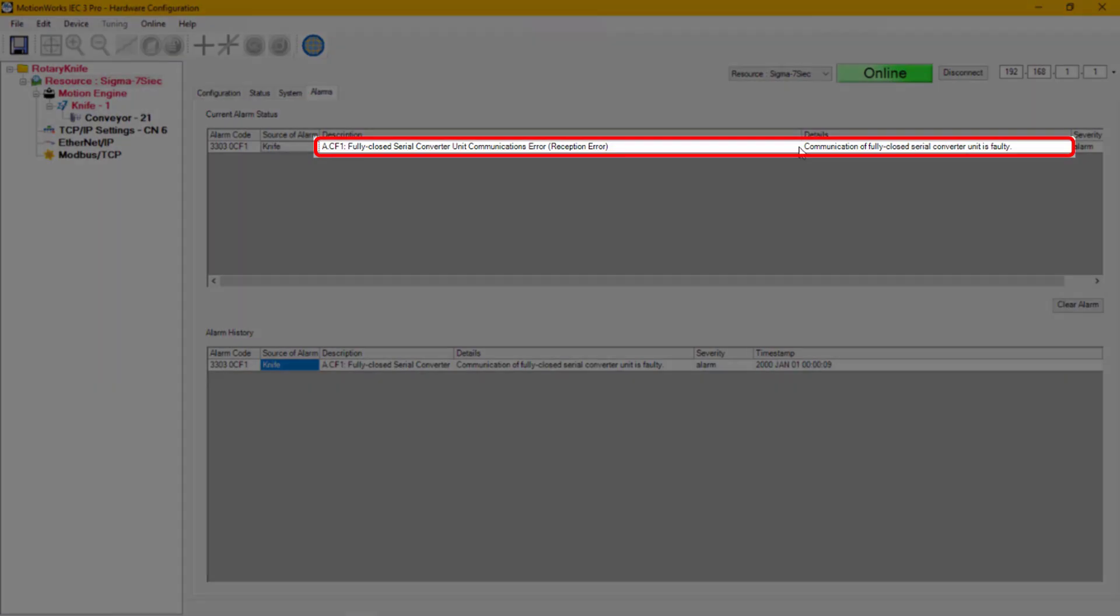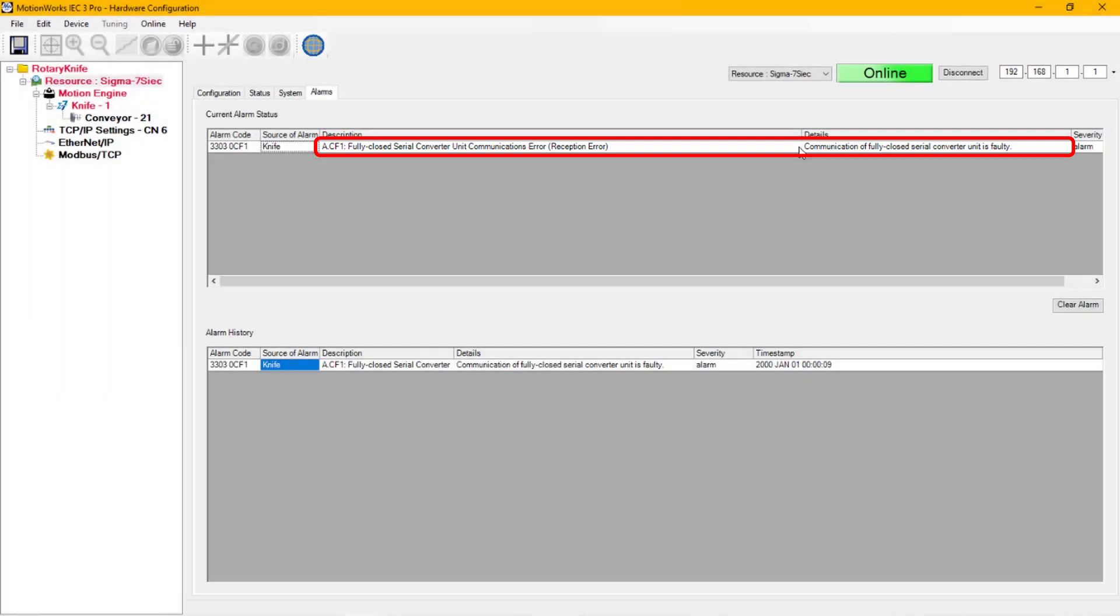When the controller turns back on, an A.CF1 alarm will appear. Basically that means that there is no encoder file loaded on the feedback option card.